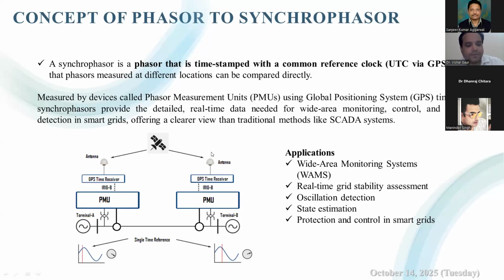These synchrophasors are measured using devices called PMUs, phasor measurement units, which use GPS signals to maintain precise time alignment, or to provide the common reference time at all locations, at location A and location B, to the PMU.